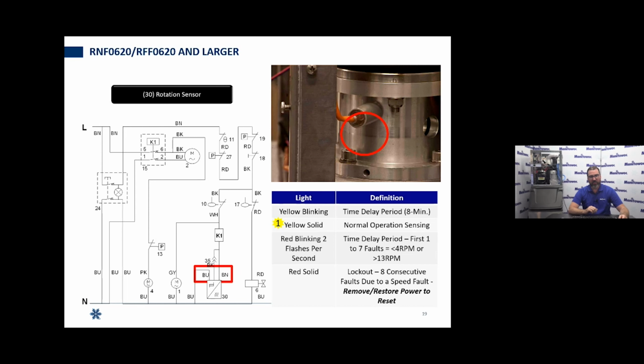Once that light's solid, that's also going to energize, one point I didn't bring up yet, our motor contactor for our compressor. So up until that point, when it's in a time delay, that compressor will not be running. So keep that in mind. If we are in a time delay period, the compressor should not be running.